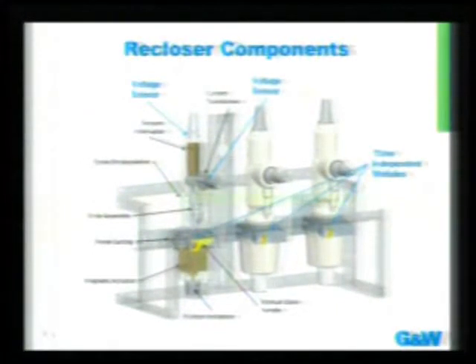Another newer innovation is that rather than having one three-phase or three-module device acting together, opening and closing all three phases at once, we now have independent modules. This allows us to have power lines coming out of the recloser that feed different neighborhoods, maybe three different ones. With independent acting recloser modules, we can isolate a problem in one area and leave the other two areas untouched.